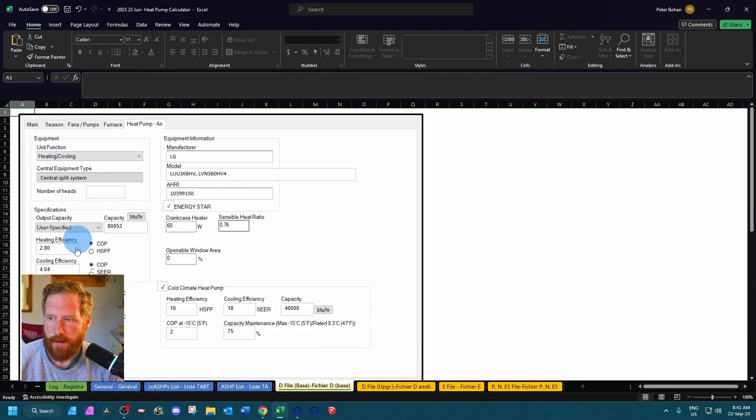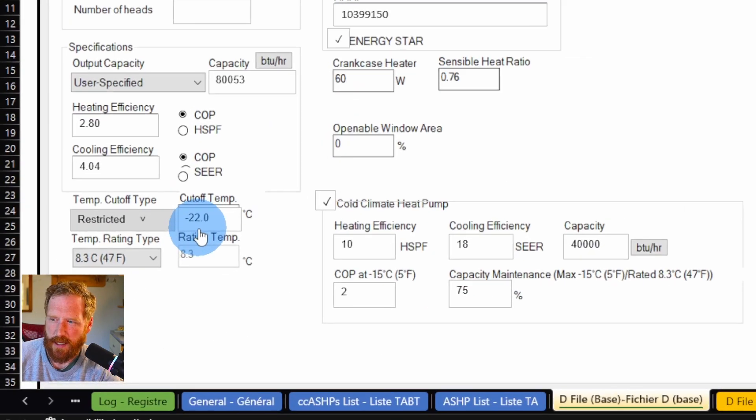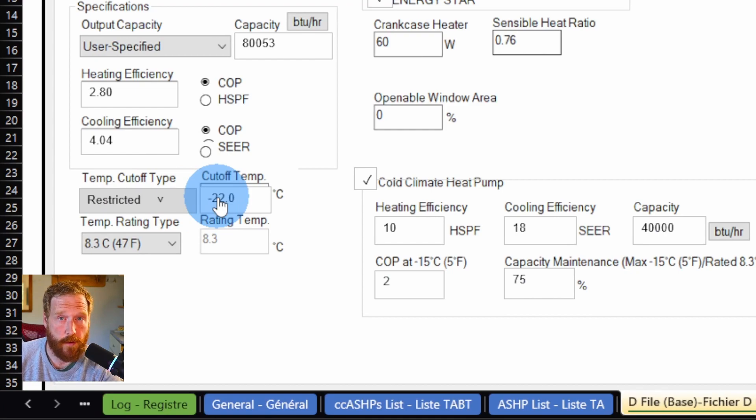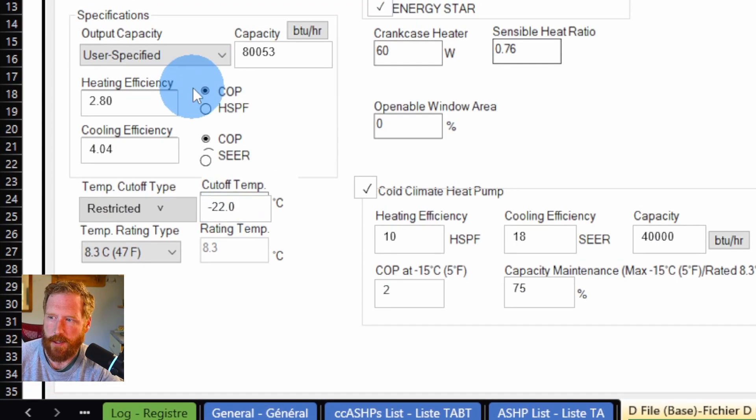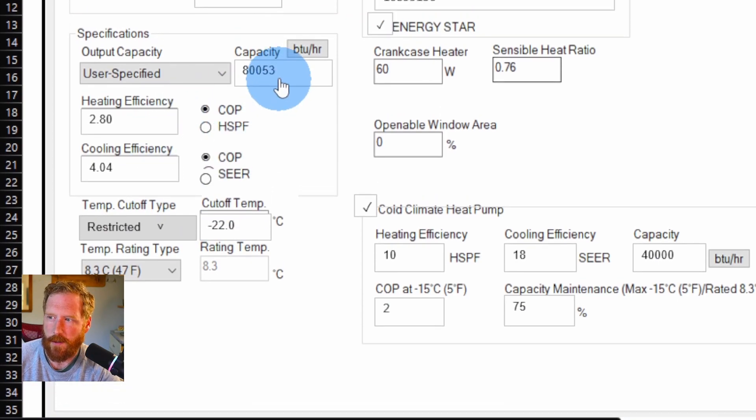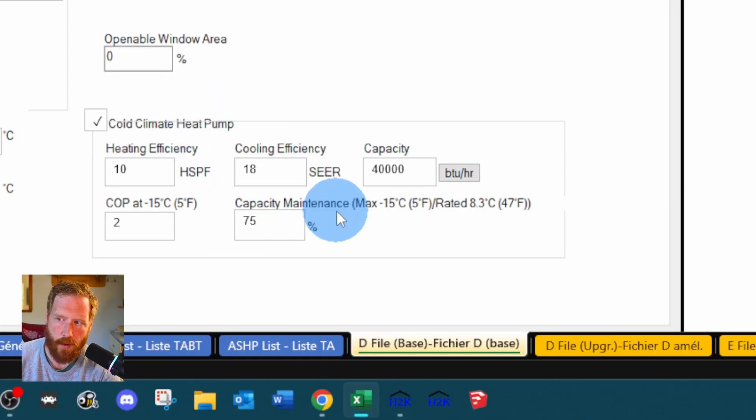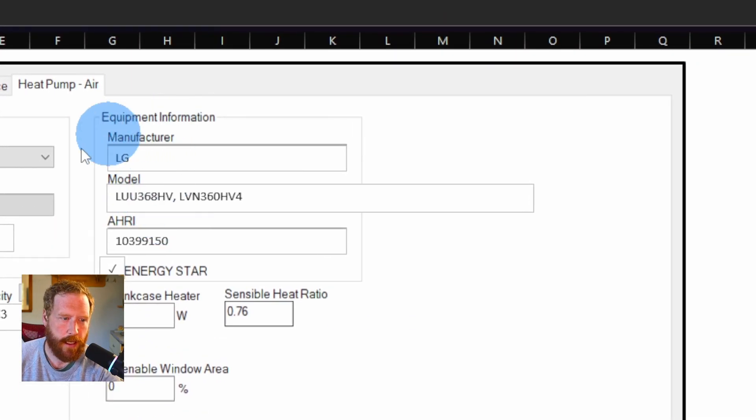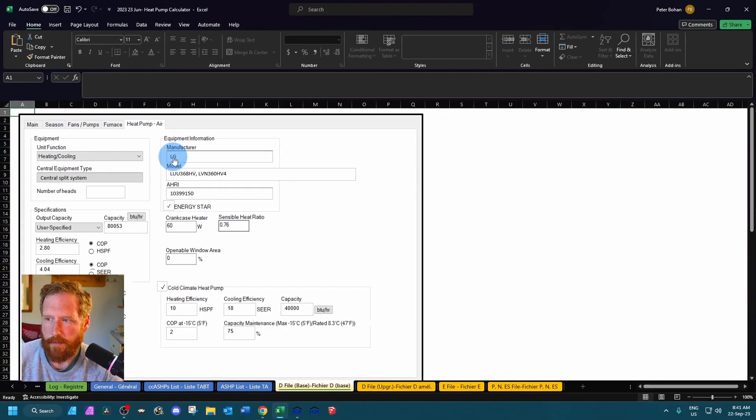Basically it's going to tell us here under the d tab, here's how we model everything. So I'm kind of in the way, at the bottom you can see it tells us it needs to be restricted at negative 22 Celsius, which is negative 7.6 Fahrenheit. Here's the COPs to use. Here's the capacity. Here's our cold climate information. And here's how we put in our make and model and how to model it here as well. If it was mini split it would tell us how many heads to put in.